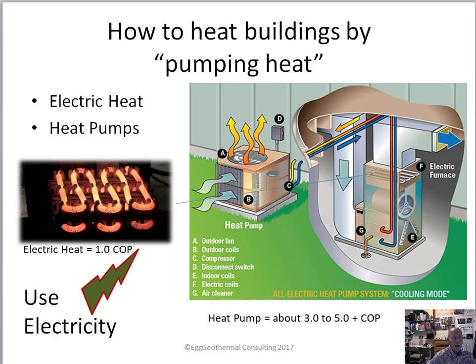Buildings are heated with heat pumps by the pumping of heat. This image shows a building that's acting kind of like a refrigerator. Think of a refrigerator sitting in your kitchen and it's trying to cool this building. In order to cool it, you see the blue arrow here — it needs to remove heat from the building. So on this air source heat pump example, it's pumping heat from out of the building to the outside. This is an electric air conditioner, which is essentially a heat pump. They use electricity and they use about one unit of energy to pump about three units of heat.